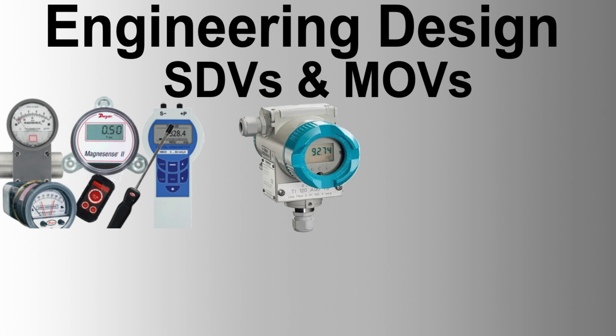Actuator design. Due consideration shall be given to the compatibility between the actuator assembly and the valve based on torque requirements. The actuator maximum output torque at maximum hydraulic network pressure shall not exceed the valve stem maximum allowable torque. Compact actuators shall be offered by the supplier. Hydraulic damping shall be provided to prevent slamming of the valve at the end of the stroke.